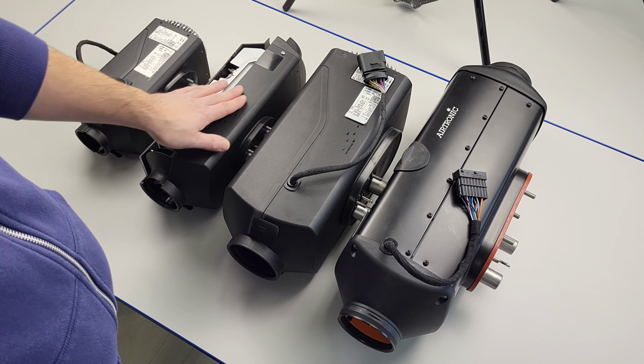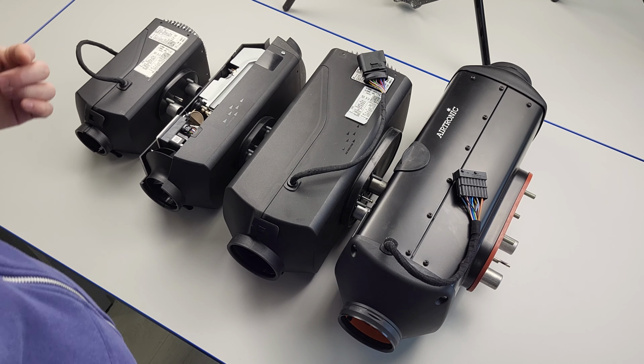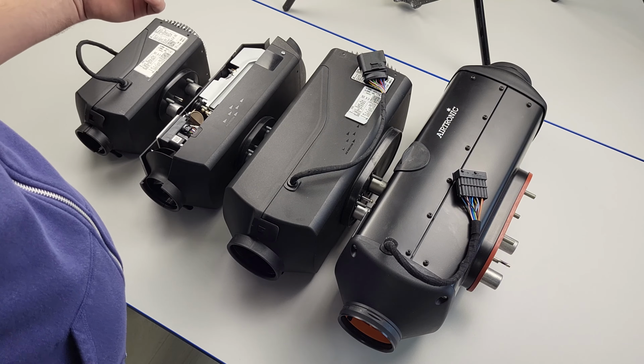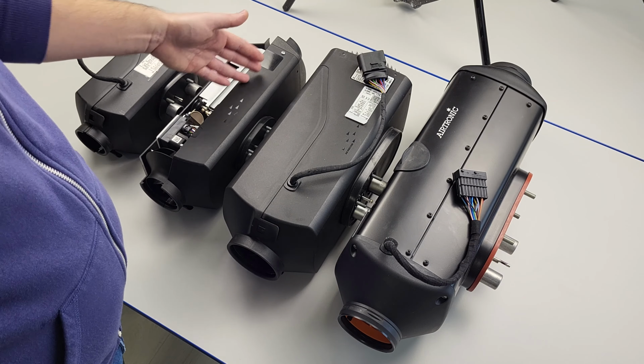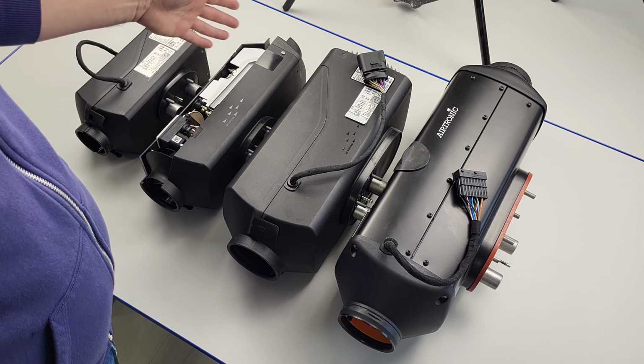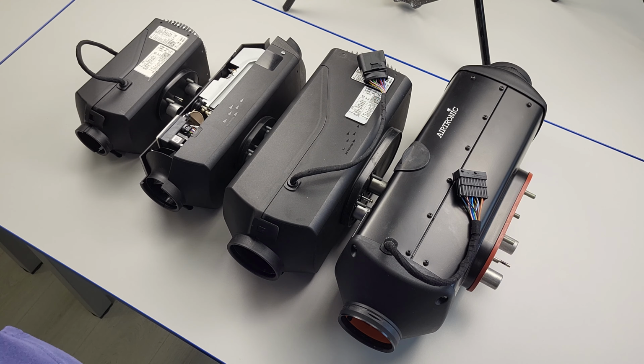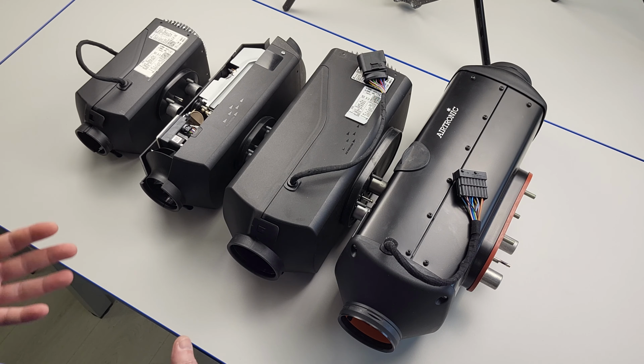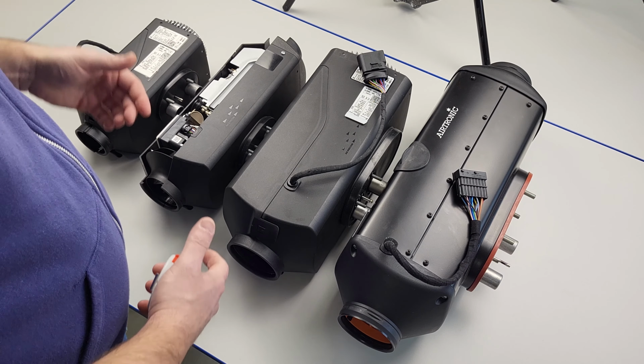Actually, what I've seen, these 4 kilowatt heaters in some OEMs sold as 3.5 kilowatt heaters. So a little bit less, we can go lower, but probably we cannot go higher, because then probably the airflow is not enough and so on. There are physical properties of the heater. So the next step is to make the heater bigger. If you want more power, we need a bigger heater, a physically bigger heater, not just on the label.